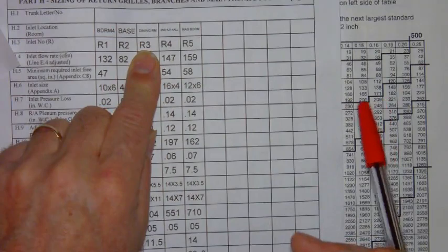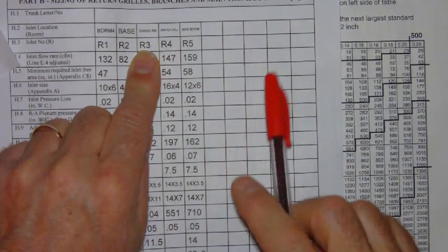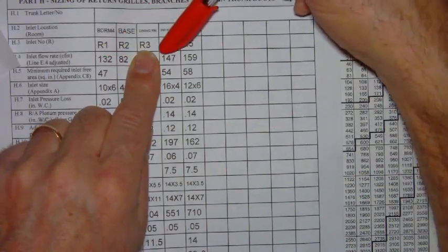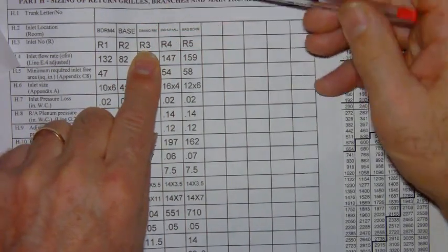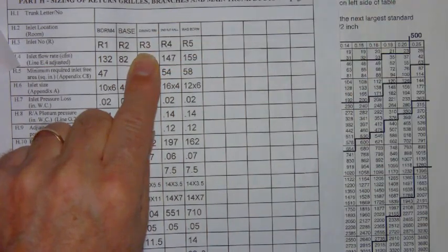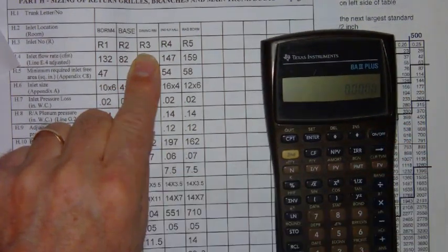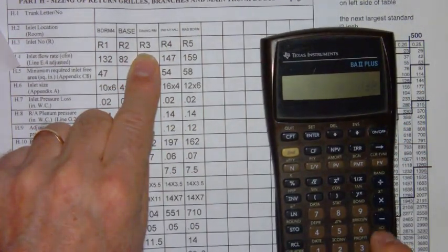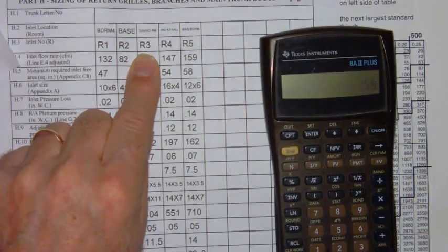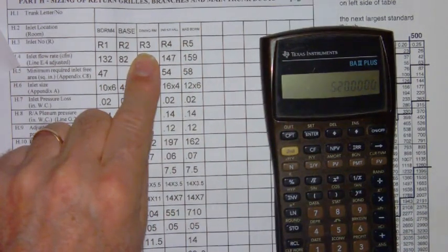At this point, we know that the total design airflow rate is 710 CFM. So we've been able to establish these 4 returns. All that's left is the dining room return, R3. To establish the amount of return air for R3, you would simply add up the 4 returns that you know, and that gives us a total of 520 CFM.